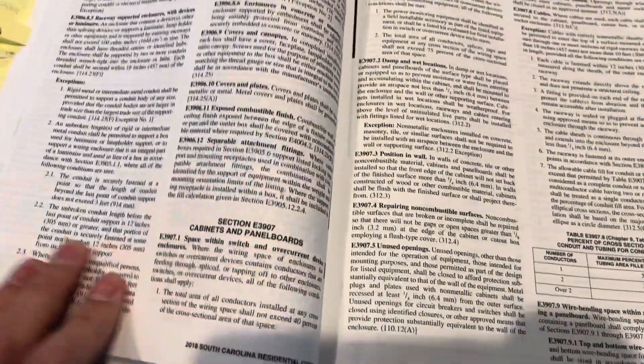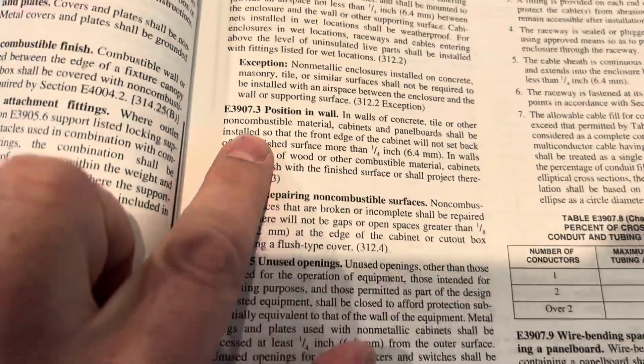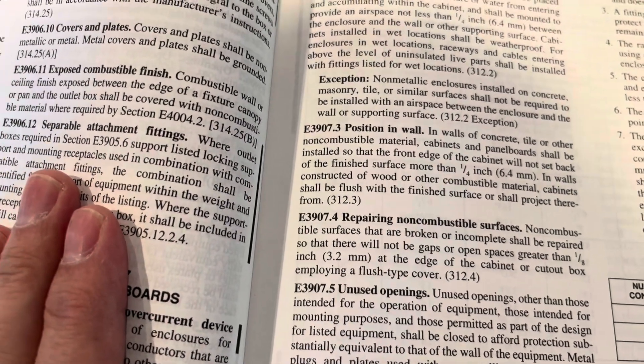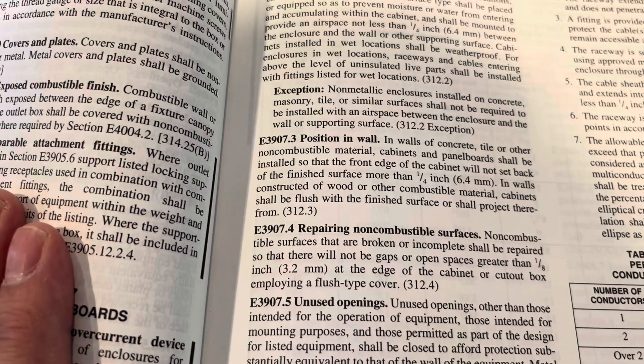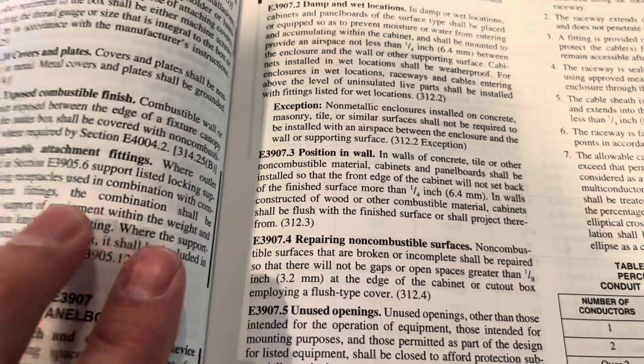If we turn to page 716, this is going to be cabinets and panel boards — that's what we were just inspecting. We'll scroll down to code number E3907.3, position in wall. In walls of concrete, tile, or other non-combustible materials, cabinets and panel boards shall be installed so the front edge of the cabinet will not set back of the finished surface more than a quarter inch.